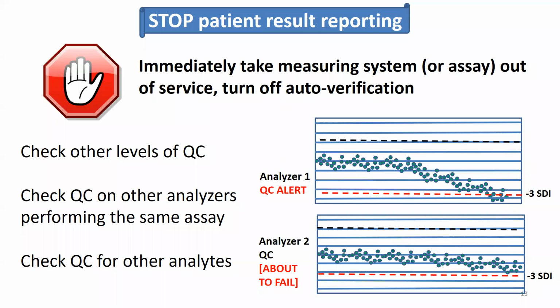That would clue you in that the event is due to something in common with multiple instruments, like the reagents, and would suggest that you need to take the assay offline on more than one instrument. You definitely want to look for other QC values that are about to fail the QC rules, so you can gain more insights into the nature of the problem and can figure out which assays or instruments you need to immediately take out of service.